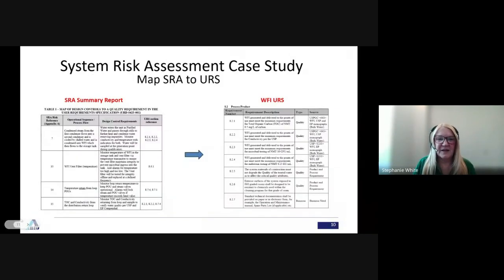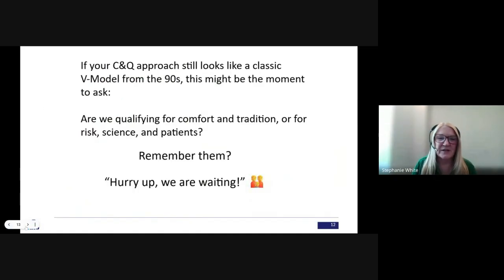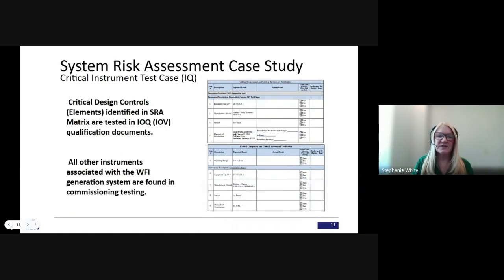A system risk assessment—here's a test case out of a protocol. In the WFI system total, not just the generation system but along with the tank and distribution system, when we did the entire risk assessment for all those boundaries, we determined there were about six critical instruments that needed to be monitored, trended, sampled, and things of that nature. So we identified those.